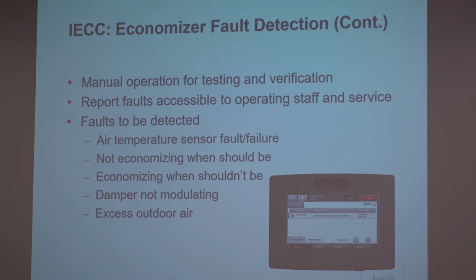So there's other requirements too that have to do with manual operation. You have to be able to override the unit controls to do some testing and validation, having those fault reports accessible, and then here are some of the faults that have to be annunciated. So I have a unit that I built for the ASHRAE show in 2013, 15, I built a unit that I could break one of the sensors and show the annunciation happening on the unit controller. So you can sort of see how that's working. And this is a really good, I think, improvement to our suite of packaged products.